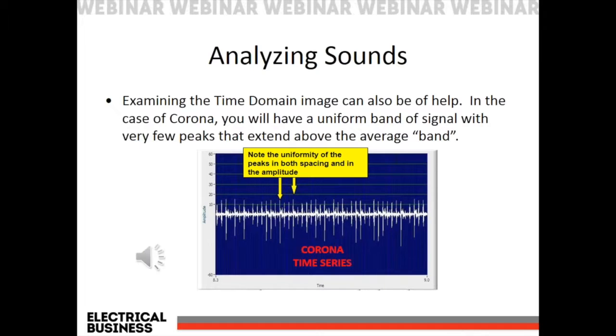Infrared is a great technology, but working with all my friends at FLIR, they'll tell you that most infrared cameras will not see corona because it does not create enough heat. It's just ionizing. Ionization does not create heat. Therefore, it is not a good failure mode for IR to detect. But again, this is why we use multiple technologies, right?